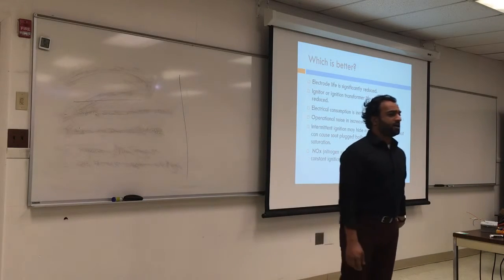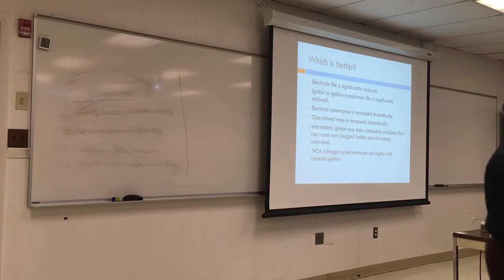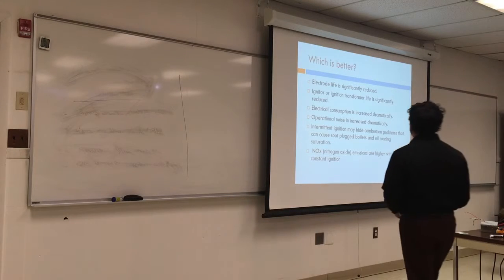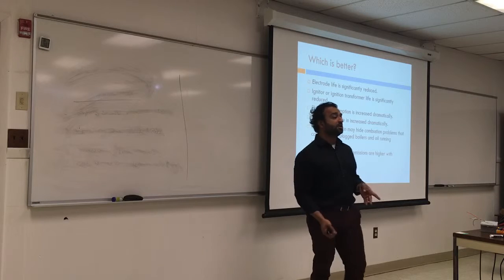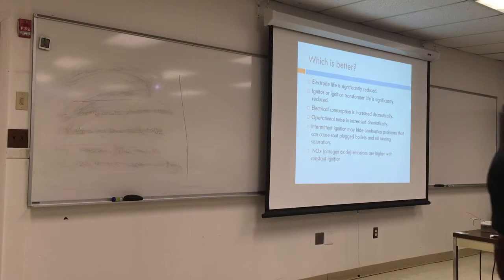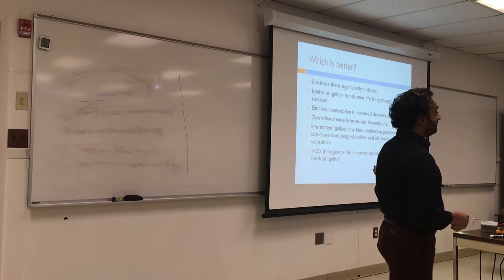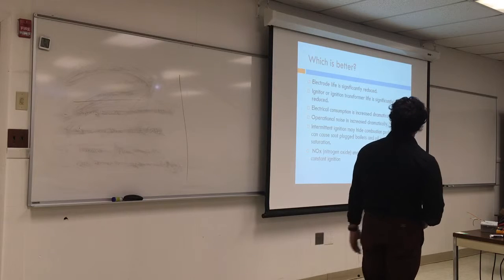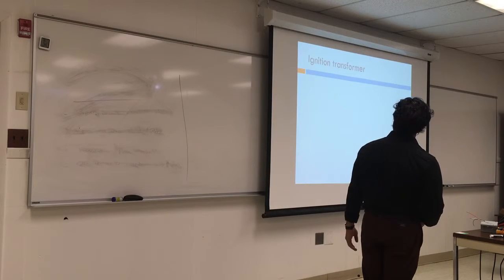NOx, nitrogen oxide. Nitrogen oxide happens when you have too much flame burning at the wrong temperature, and it will be much higher if you have constant ignition. That's why they stopped using continuous ignition. Even though it makes the fire sure to happen, it's better to have interrupted ignition. Massachusetts is a low NOx state, so they try to make flame and fire without producing a lot of nitrogen oxide. Nitrogen oxide is not good for the environment, so we try to reduce most of it. If we have bad combustion, we will probably have nitrogen oxide. So this is one of the reasons that you don't want continuous ignition.